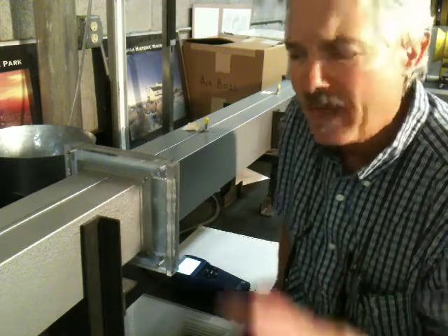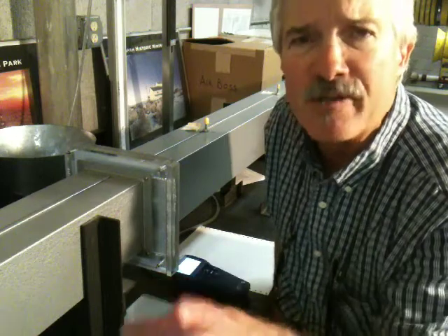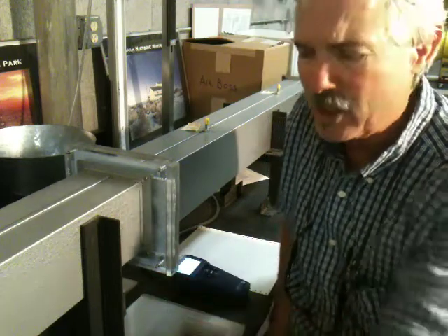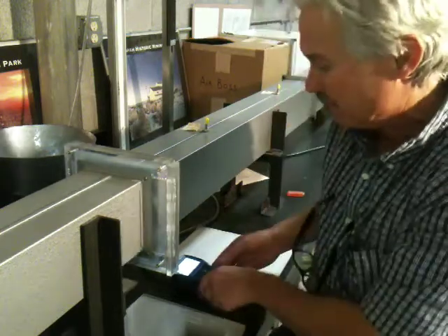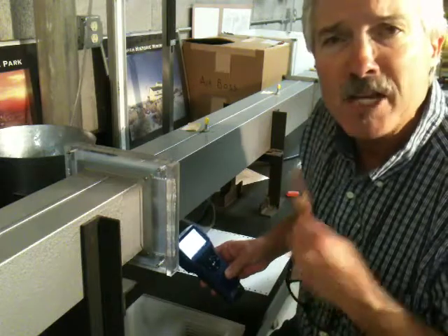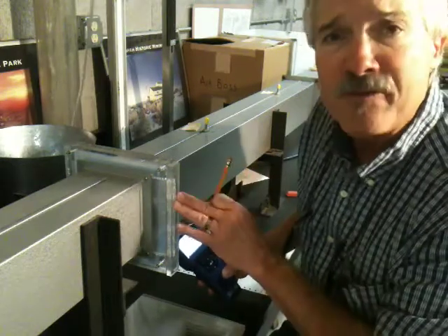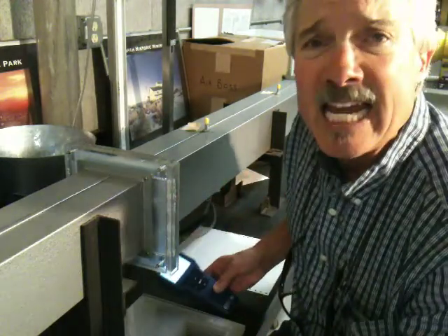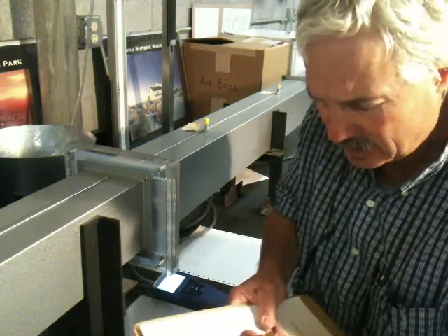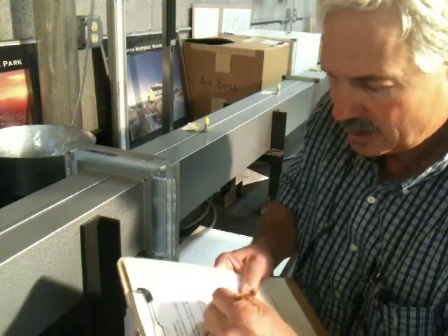And I didn't talk about this before, but we will email you filled in data sheets with all of this data. So you don't need to try to record anything I'm writing down here. I'm just showing you how we would do the exercise. Okay, so the delta static pressure at full flow is 1.880 inches of water. So I write that down here under delta static P.